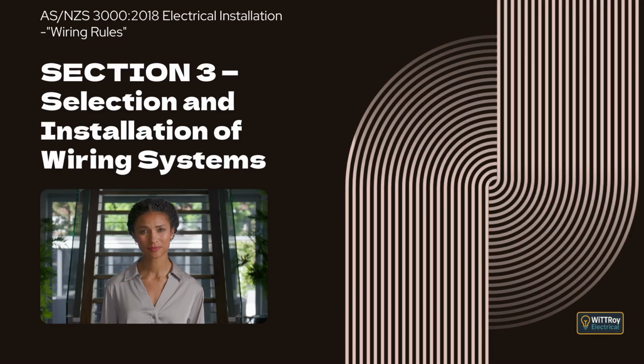Clause 3.8.2.1, Color identification by sleeving or other means. This clause explains that sleeving or other color identification methods may be used at terminations to identify conductors where appropriate, provided the identification is durable, color-fast, and compatible with the installation. Clause 3.8.2.2, Sleeving of existing earthing and bonding conductors. This clause explains that existing bare or green earthing or bonding conductors installed under previous rules may remain, but where alterations or repairs create new terminations, those conductors must be sleeved green and yellow at the new connection points.